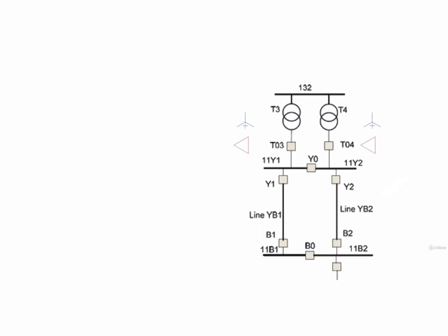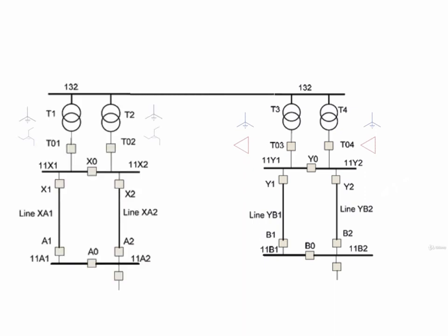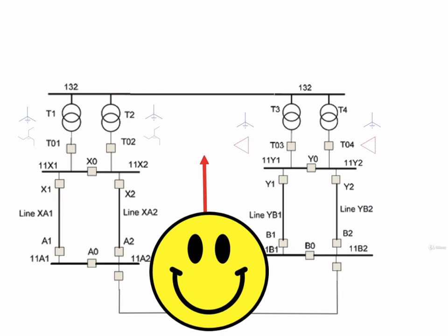Now, let's revisit our hypothetical growth system, and we still have the existing station with two Y to delta transformers ultimately feeding the low voltage distribution grid. This time, however, it grows and it builds into a Y zigzag transformer station. As the system continues to grow, at some point it would meet for logistical reasons. Again, it might seem practical to parallel the systems. This time, the feeders are in phase with a much happier outcome.